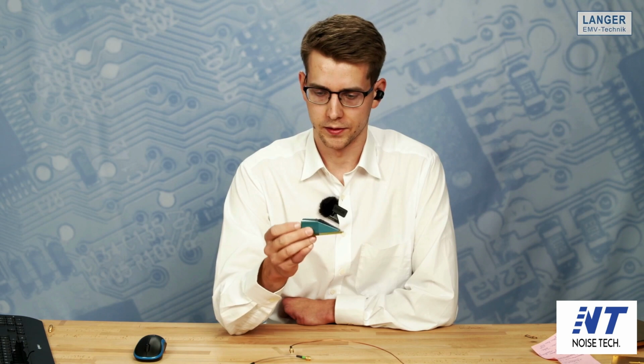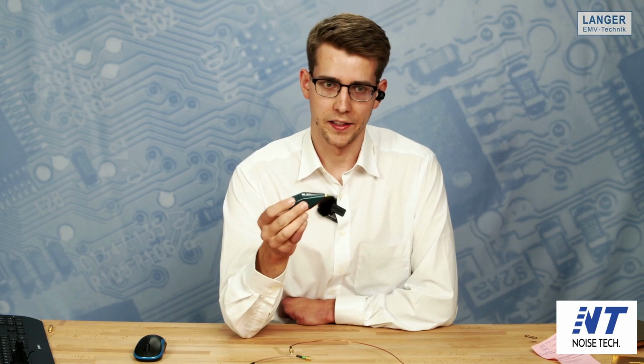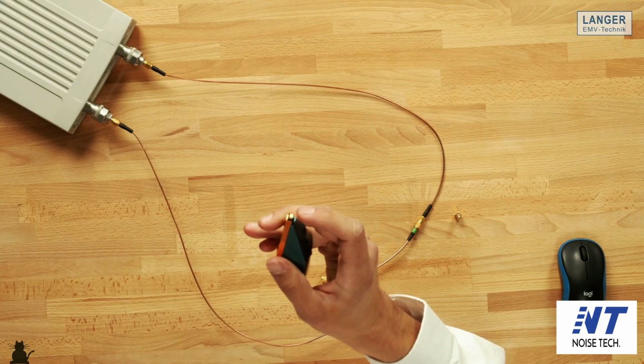So, some short information about the P500. This is a high-frequency power injection probe, and you connect a high-frequency input here with the SMA connector, and then you have a pin contact. So this then leads to the pin contact in the front and goes directly into the circuit. What is also part of this probe is that at this point of pin contact, you can also measure the voltage and also the current that goes into the pin.